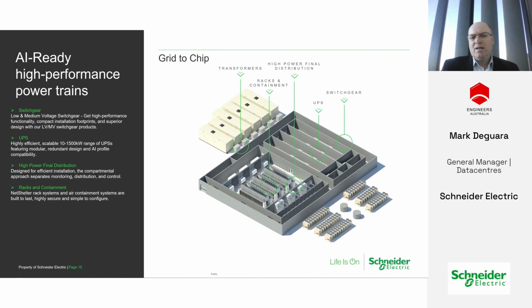To give you an idea, a high performance compute rack today is 1,800 kilos and beyond. Think about that, 1.8 tons sitting in a fairly small footprint, nominally 800 mil by 1,200 mil. Considering that, how do I account for that? If I'm building a new data center and can load my floors for it, yes, I can work with it. But if I'm in an existing facility with multiple stories, deploying 10, 15, 20, 30 of these 1.8 ton racks, can my existing floor take it? Can my goods lifts take it? How do I deploy that?